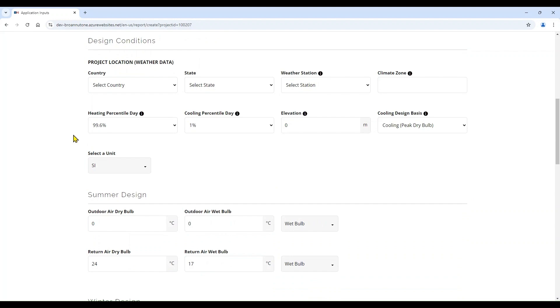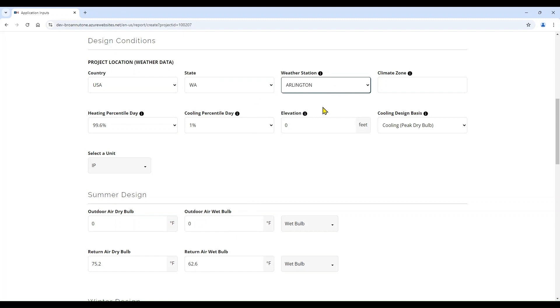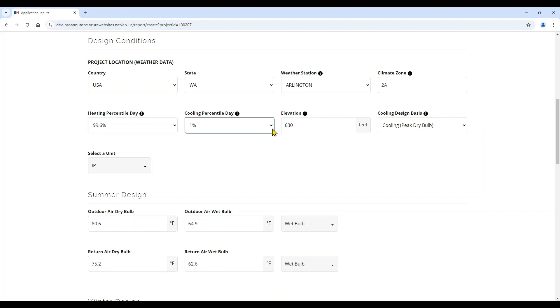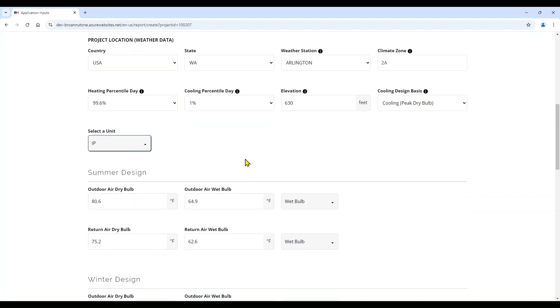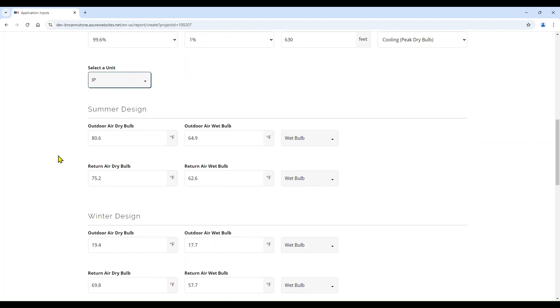The next step in the project creation is based on your project location and selecting the related weather data. We'll start with the country selection, the state, and the weather station closest to your project location. As you can see, information has been pre-populated and this is being pulled from the ASHRAE climate zone database. We have the ability to change the heating percentile day, the cooling percentile day, as well as the cooling design basis. You will notice that based on the country, the units have been pre-selected, but you do have the ability to change those.